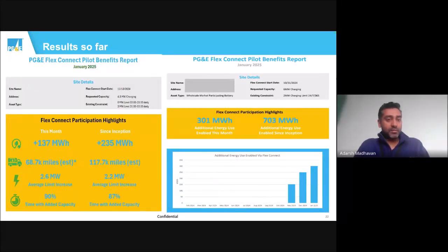The requested capacity is 4 megawatts. The amount of available capacity between 3 a.m. and 9 p.m. is 0, and they are able to charge at 3 megawatts between 9 p.m. and 3 a.m. every day. But with FlexConnect, in the month of January, we were able to give them additional capacity 87% of the time.